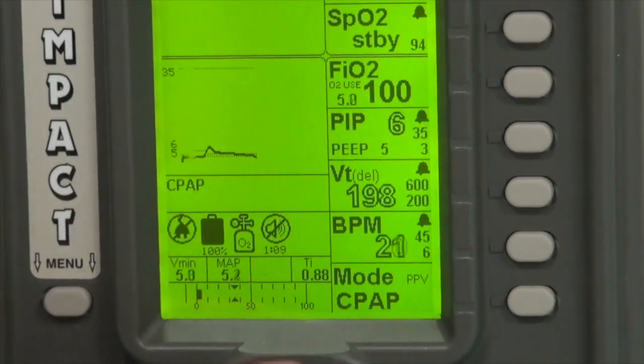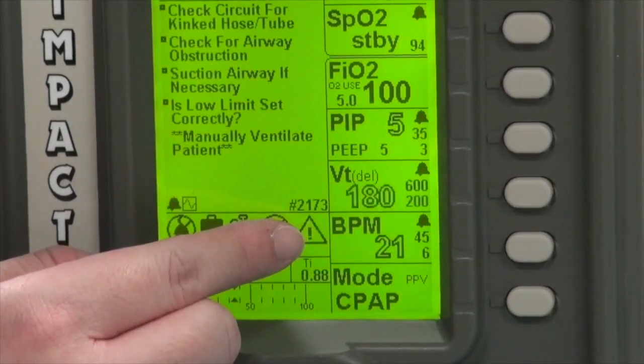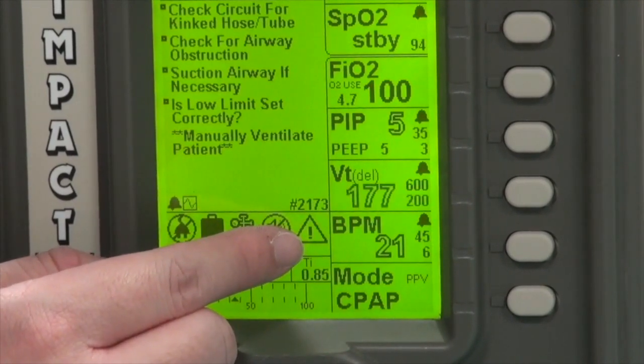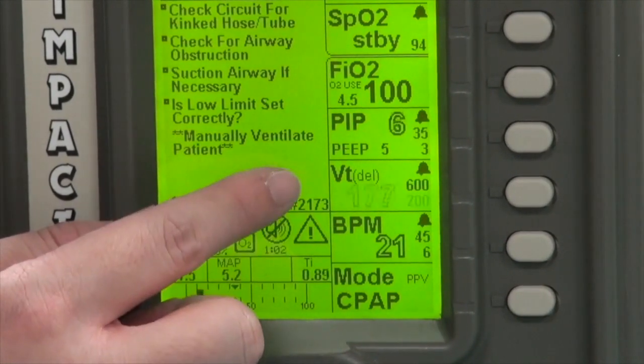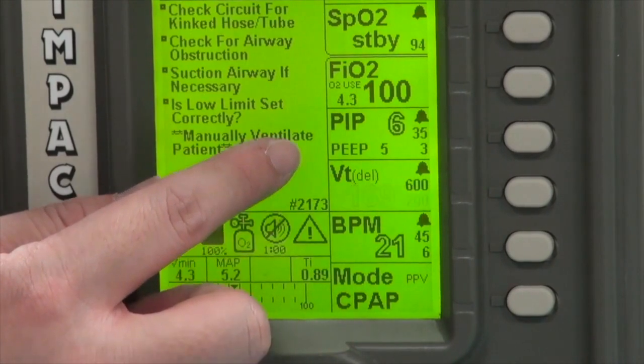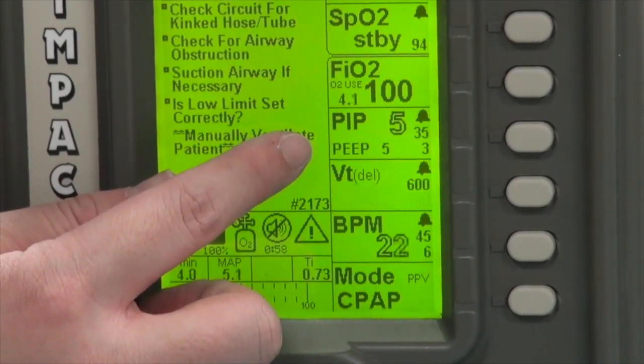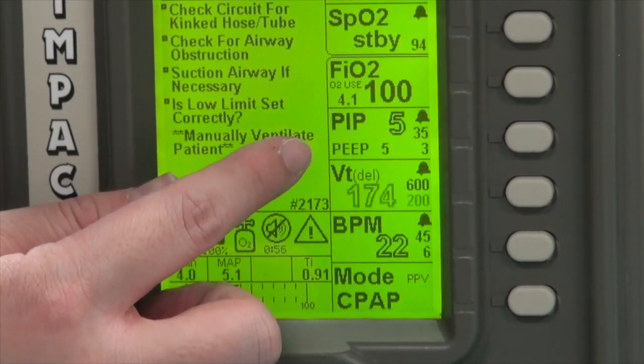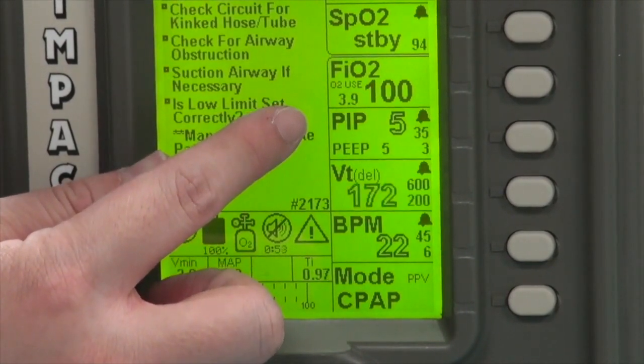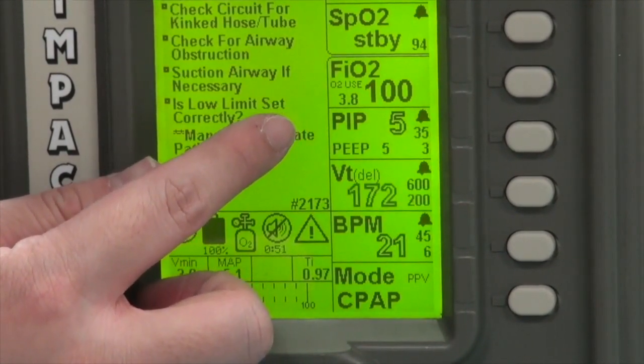Going upwards, you see that the breaths per minute now are hollowed out numbers. This means that it's a measured value and not a setting. Tidal volume is also a measured value. We have PEEP over here, which is still a setting, as shown by the black numbers. We have peak inspiratory pressure. However, you do not see pressure support.